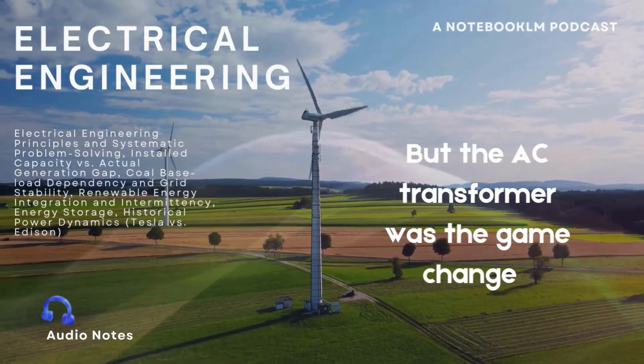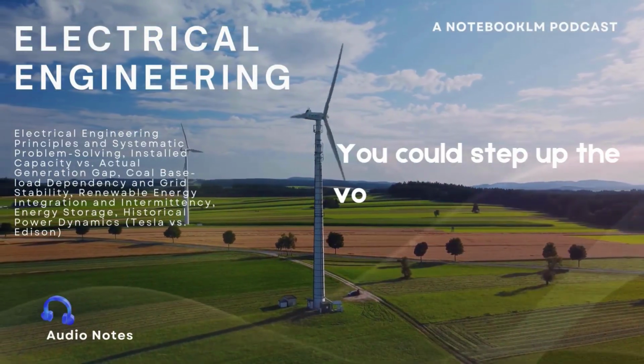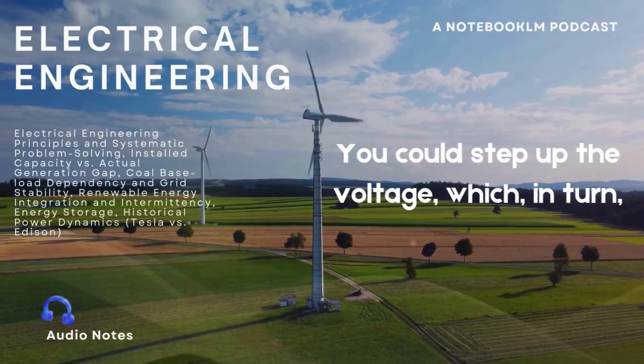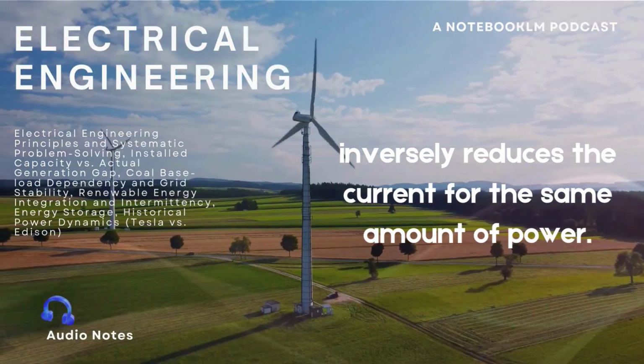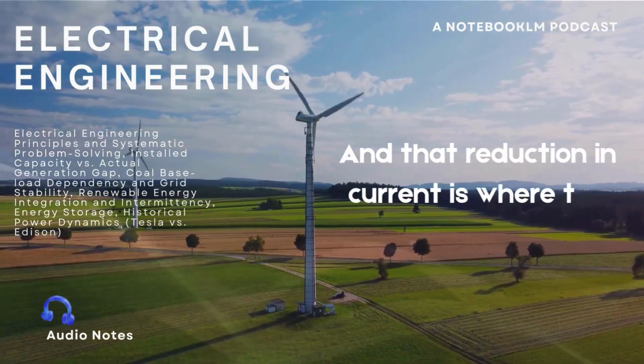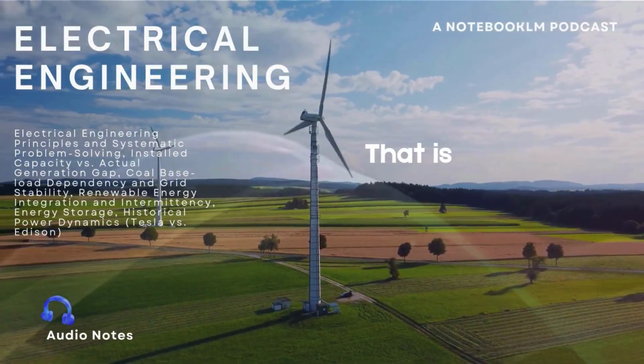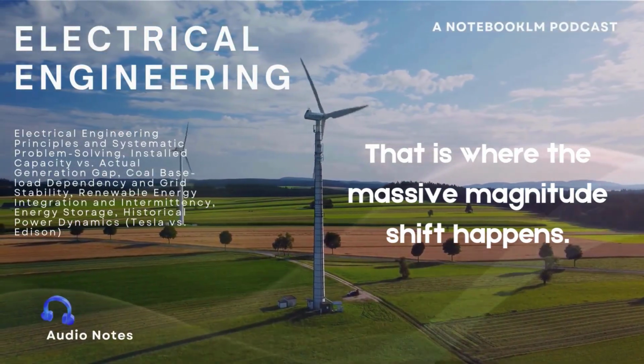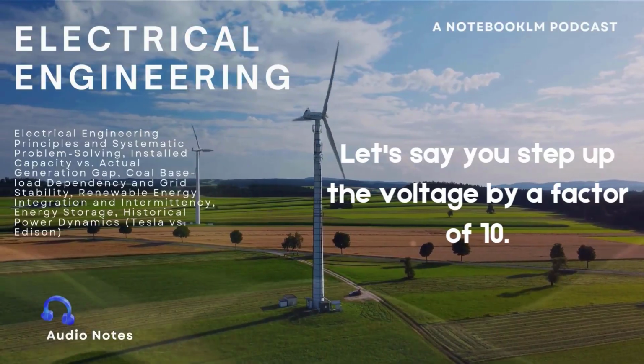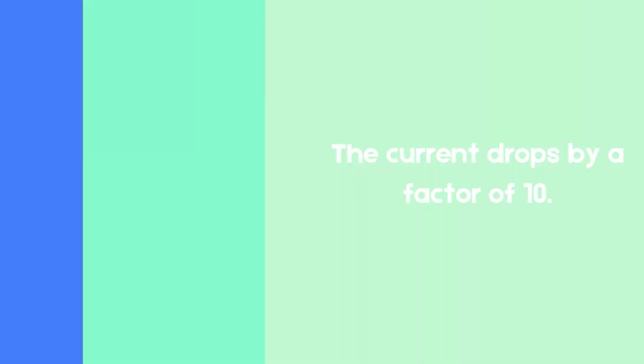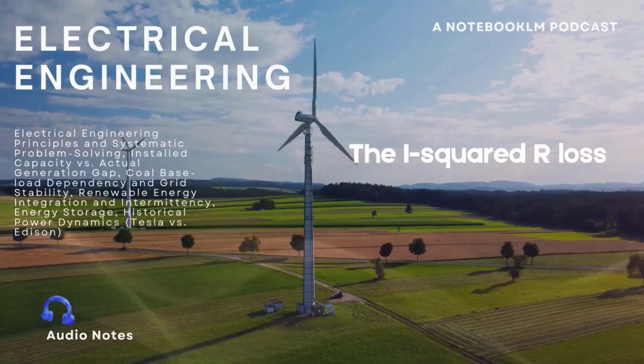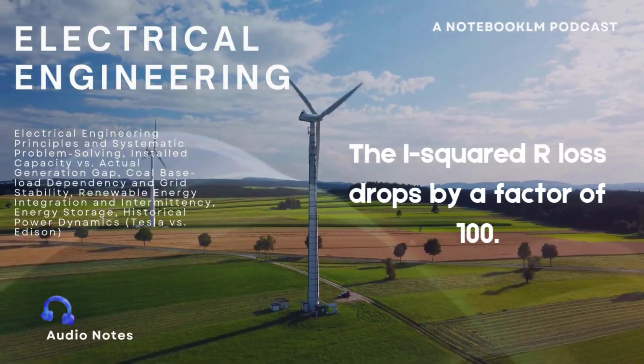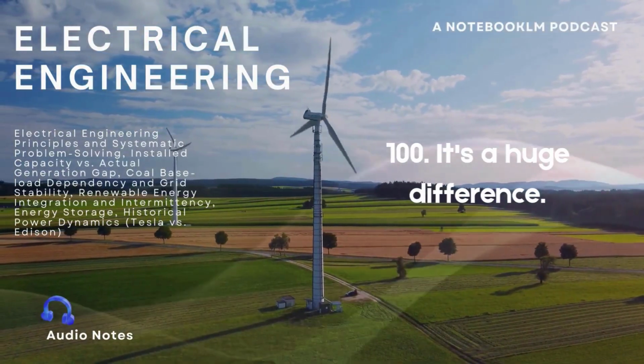But the AC transformer was the game changer. You could step up the voltage, which, in turn, inversely reduces the current for the same amount of power. And that reduction in current is where the magic happens. That is where the massive magnitude shift happens. Let's say you step up the voltage by a factor of 10. The current drops by a factor of 10, but because the losses are squared, the I squared R loss drops by a factor of 100. 100. It's a huge difference.